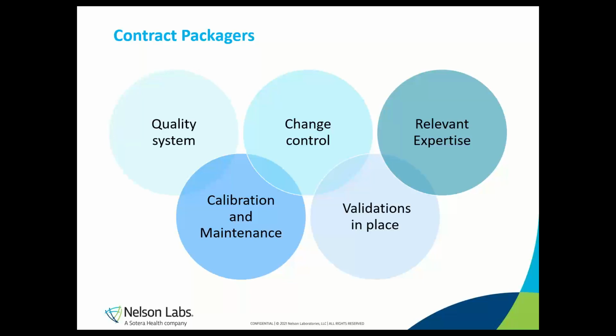Make sure the contract packager has a quality system in place that is appropriate for the medical device or pharma industry, and that they have the relevant expertise in sterile barrier packaging and are familiar with the degree of regulatory compliance expected of our industry. Make sure they have change control procedures in place and will notify you of any changes that they make so that you can assess what impact those changes may have to your product and validation. Verify they have validations in place for the equipment and process that meet the requirements in ISO 11607. And make sure they have calibration and maintenance schedules for their equipment.